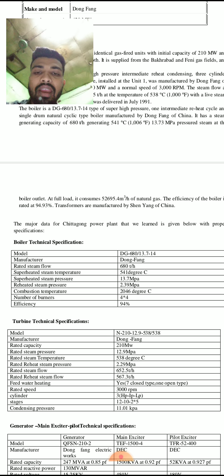The boiler is a DG-680/13.7-14 type, super high pressure, one intermediate reheat cycle, single drum natural circulation type boiler, manufactured by Dongfang in China. It has a steam generating capacity of 680 tons per hour, generating 541 degree Celsius, 13.73 megapascal pressurized steam at the boiler outlet.